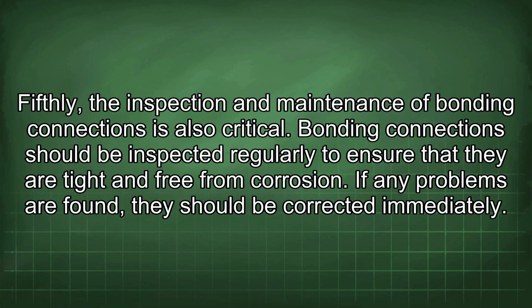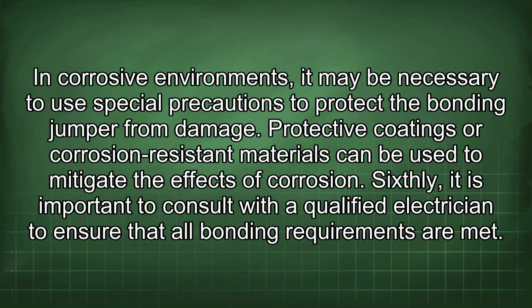Fifthly, the inspection and maintenance of bonding connections is also critical. Bonding connections should be inspected regularly to ensure that they are tight and free from corrosion. If any problems are found, they should be corrected immediately. In corrosive environments, it may be necessary to use special precautions to protect the bonding jumper from damage. Protective coatings or corrosion-resistant materials can be used to mitigate the effects of corrosion.